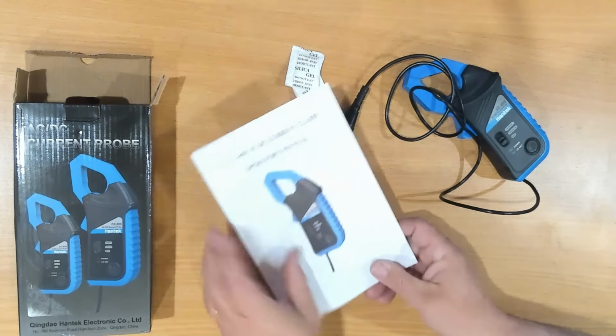So there is actually no power factor involved here. It is all harmonic distortion. The power factor is actually spot on. It's just all distortion. Most passive power factor correction systems won't actually correct this one very well at all, whereas they will correct the previous one without any hassle. So this adapter is proving to be useful. I've still got a lot more testing to do on site just to see what other problems I've got inherent. And I think this is going to be a useful addition to my toolkit.